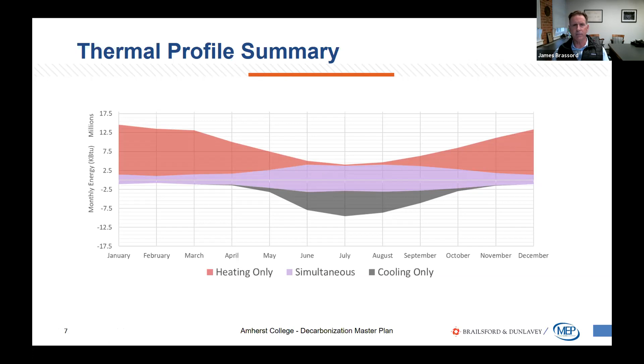But at that same point, we can use simultaneous heating and cooling to boost the efficiency of the heat pumps. In the shoulder seasons and into the summer months, there's much more overlap, and at this point we're able to run the heat pump plant at a coefficient of performance of 6, fully 600% more efficient than our current systems.